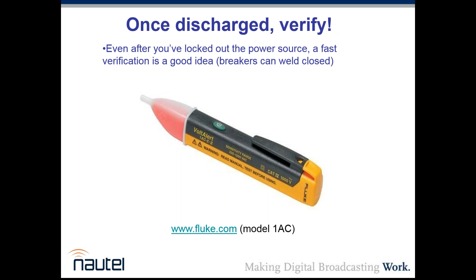Do notice as well here that the maximum sensitivity range is 1,000 volts. Yeah. There may be tube-type transmitters where that's exceeded, or even the RF stages of transmitters where that's exceeded. Oh yeah. Okay. So, definitely. Now, the other thing to think about with this, and I've got it in brackets at the top, is how many times have you opened a breaker and discovered one phase didn't open, even though the actuator moved, but it was still welded closed. Yeah.